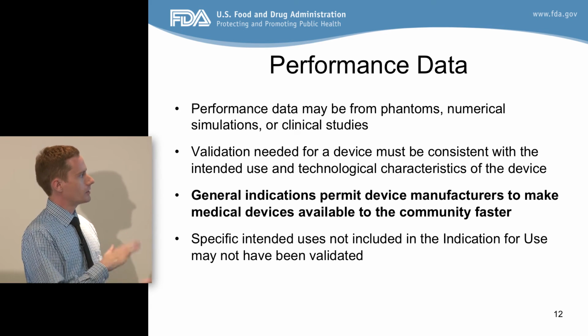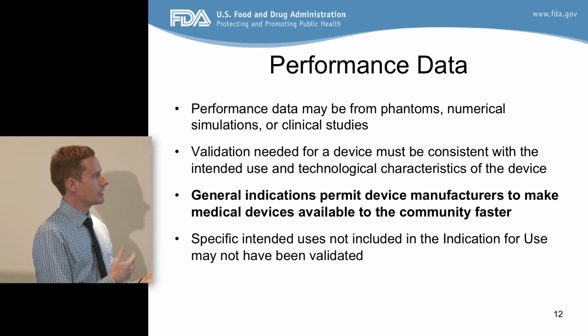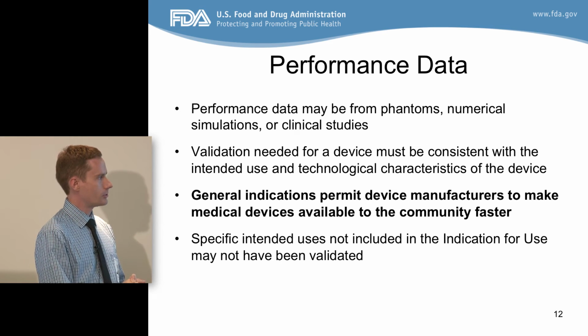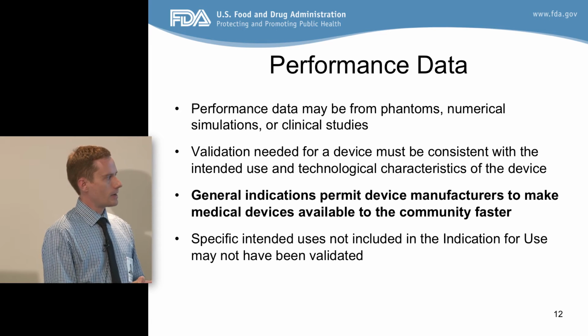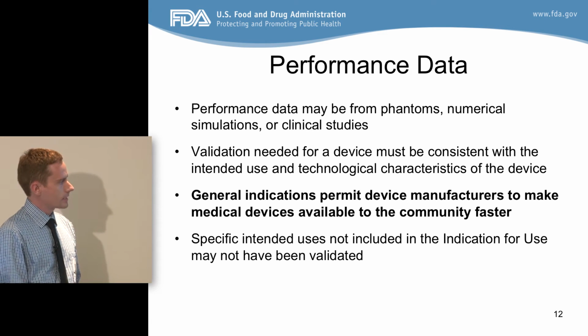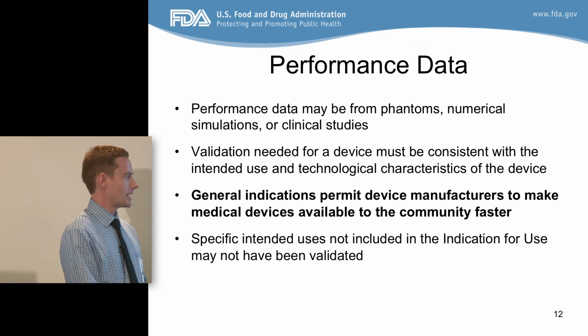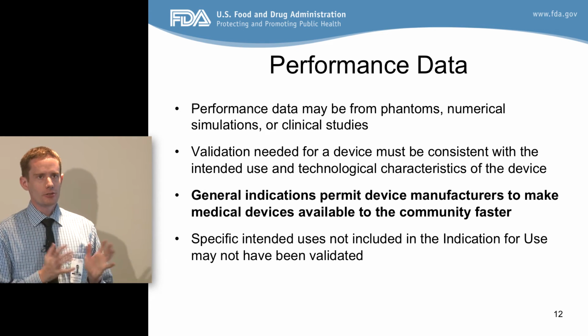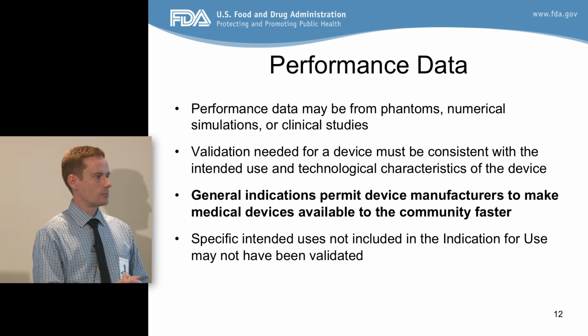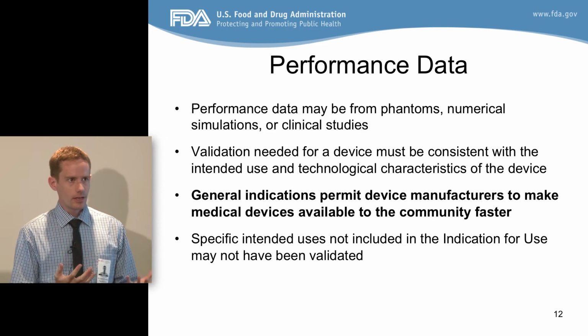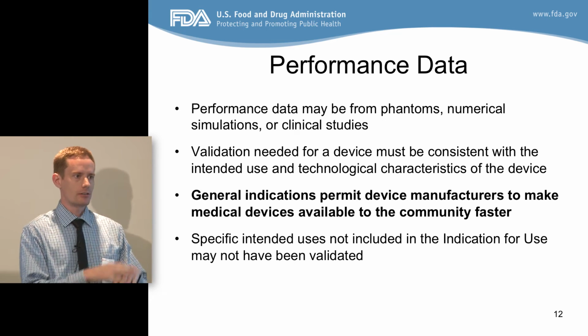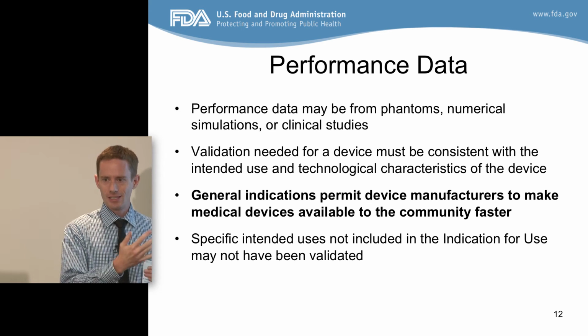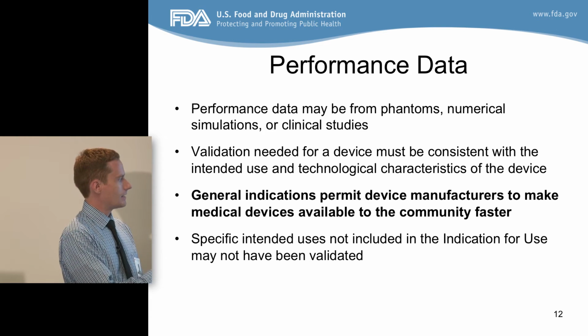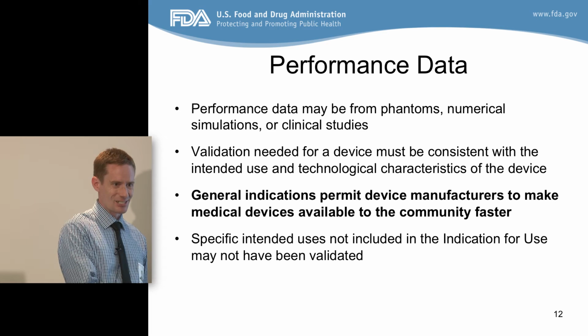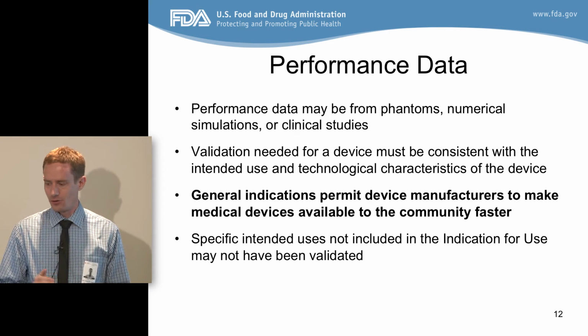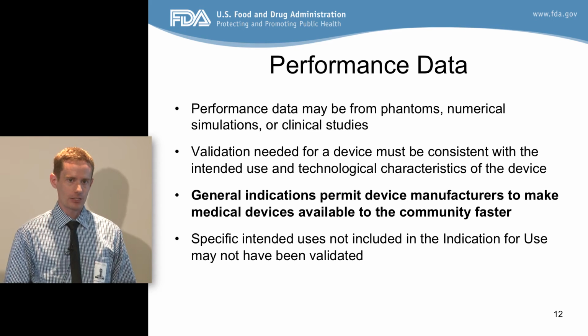As mentioned before, the general indications for use that we've seen permit device manufacturers to make medical devices available to the community faster, whereas specific intended uses not included in the indications for use may not have been validated. Let me describe this really quickly. A CT scanner is generally indicated to produce cross-sectional images of the body. We can validate that generally with phantoms or simulations, to understand that yes, it can produce cross-sectional images of a structure. But that doesn't mean that all CT systems are then cleared, studied, or reviewed by FDA for very specific clinical applications.